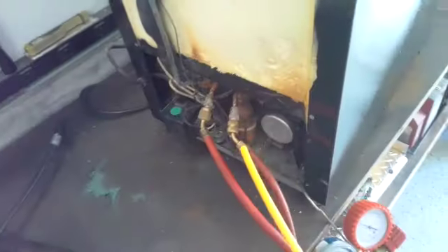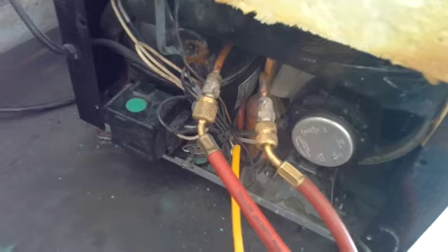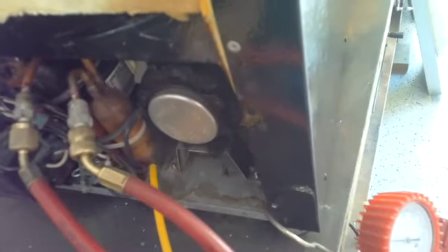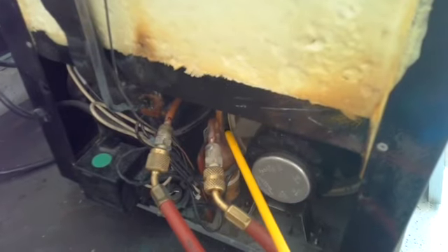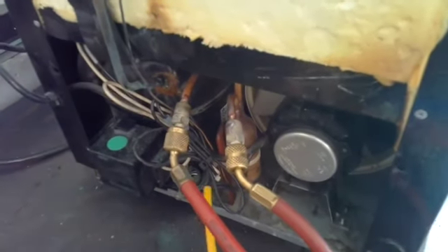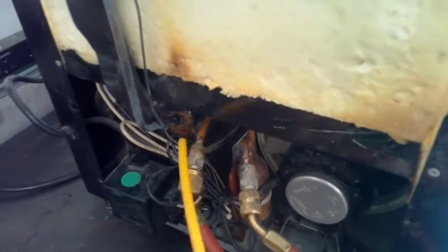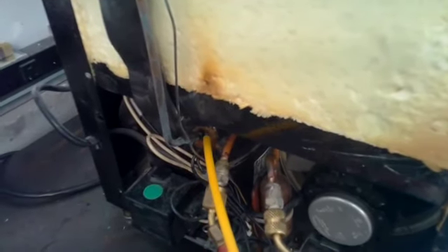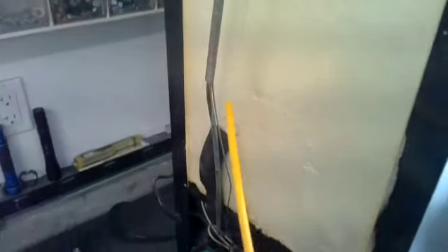Really, really slight. You know, checking all the areas where tubing is rubbing up against something or where there's moisture. Nothing here. Nothing on the capillary tube. As soon as I get right here, I hear something. So I'll try to put some soap bubbles on there and see if we can pinpoint this thing. Because if it's in here, then we have to change the heat exchanger.